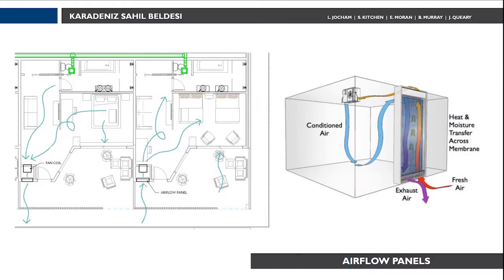Airflow panels are innovative individual energy recovery units that are integrated with the facade of the building. The polymer-based membrane with desiccant permeates moisture and heat between incoming and outgoing air. The use of these panels replaces the need for larger HVAC equipment and distribution ductwork. As a result, each space is supplied the outdoor air requirement of ASHRAE 62.1.